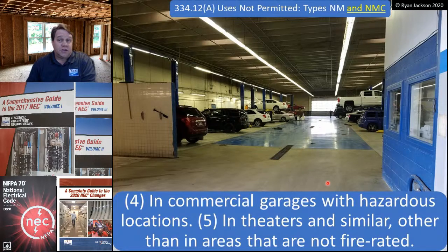Number five, in theaters and similar, other than in areas that are not fire rated. That's a dicey issue, to be quite honest. Most commercial buildings really aren't fire rated anymore. If you classify the building as fire rated, that would be like type 1A versus type 1B, or type 5A versus type 5B. That's more than we're going to get into tonight, but really, not a lot of buildings are fire rated anymore. So I think in a lot of theaters, you might be able to, but it's pretty doubtful that we would specify NM cable in such an application.